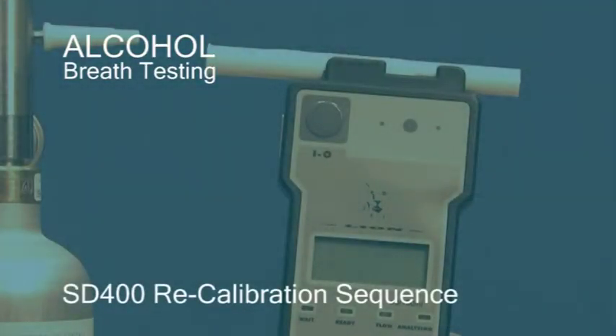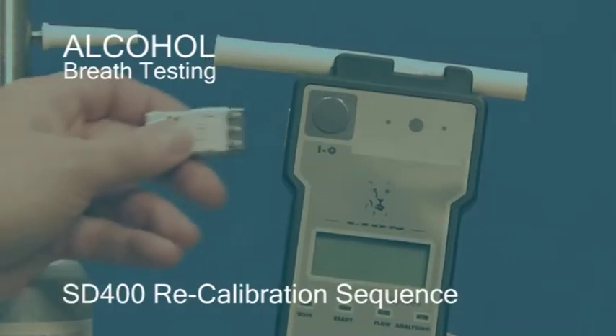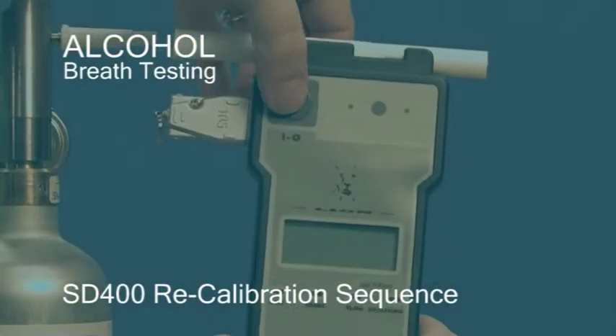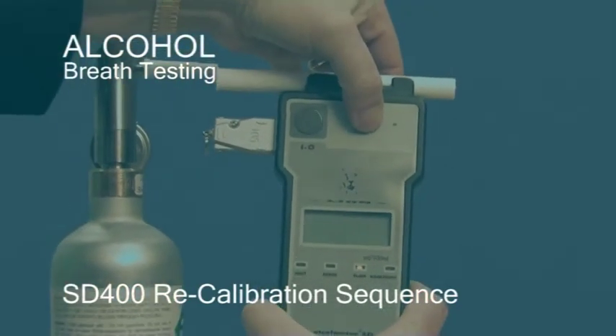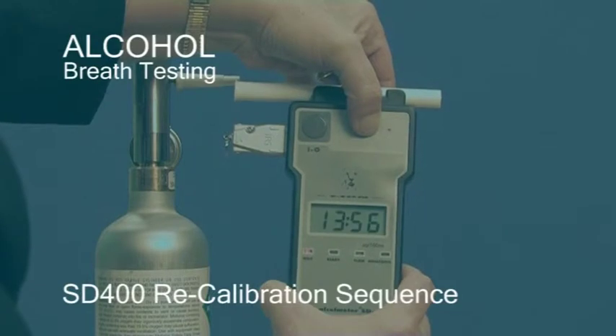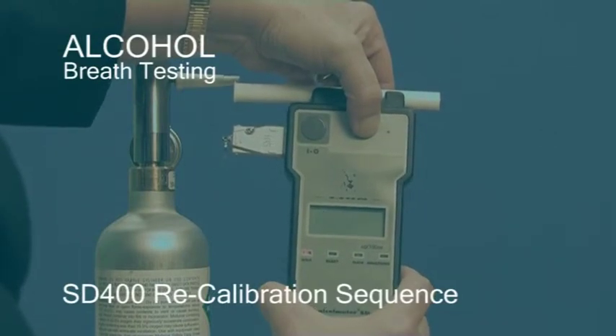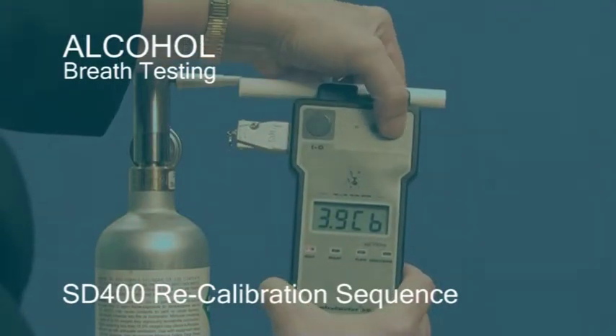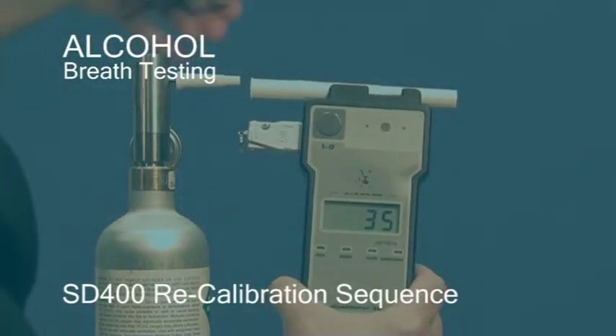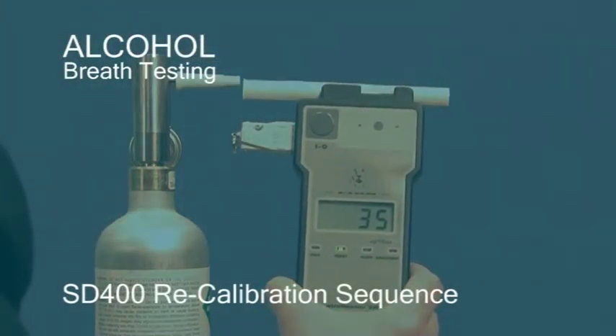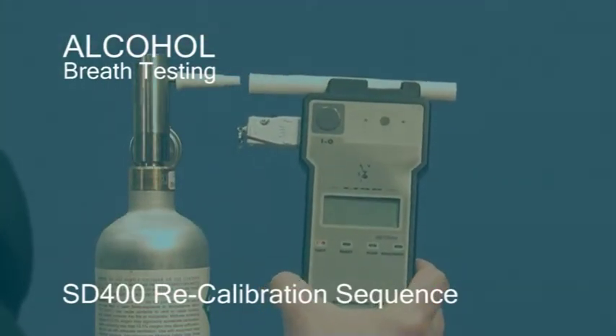SD400 recalibration sequence. Insert your dongle key. Switch the instrument on, and before the diagnostic sequence is completed, press and hold down function switch C. When a continuous tone is heard, release C and press and release function switch D. The machine will show the value of the gas it is expecting. Adjust this to match the value of the gas you will be using, using function switches B and D. Press function switch C to confirm the gas value. The reading will flash 5 times. Wait for the ready light.